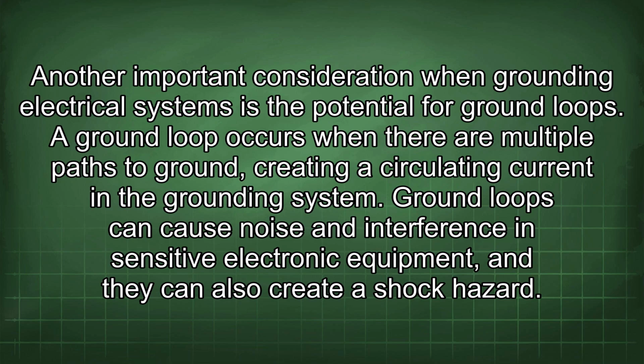Another important consideration when grounding electrical systems is the potential for ground loops. A ground loop occurs when there are multiple paths to ground, creating a circulating current in the grounding system. Ground loops can cause noise and interference in sensitive electronic equipment, and they can also create a shock hazard.